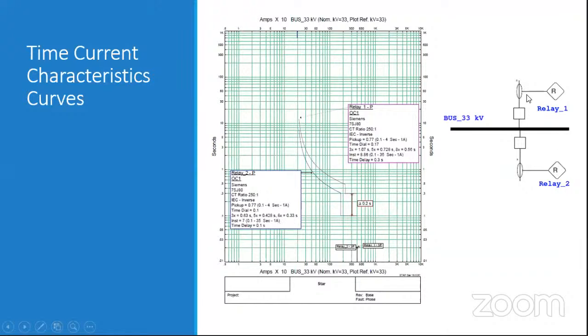For backup protection, if relay 2 fails to operate, then relay 1 will be the backup, and it will operate after a time margin of 0.2 seconds, that is, 0.1 for the downstream relay, and the time interval for relay 1 has been set accordingly with the margin of 200 milliseconds, such that this relay will operate in 300 milliseconds.